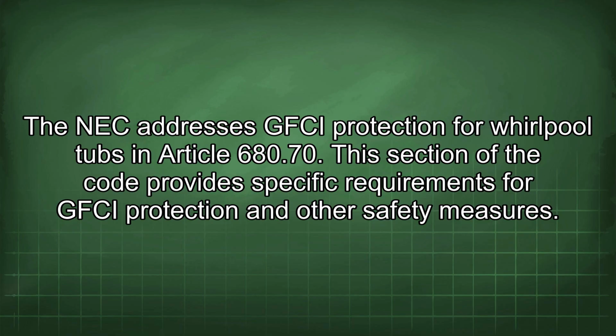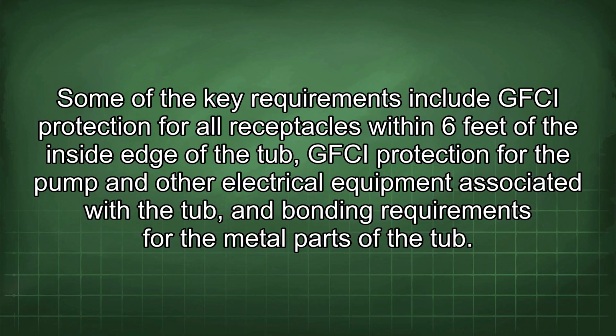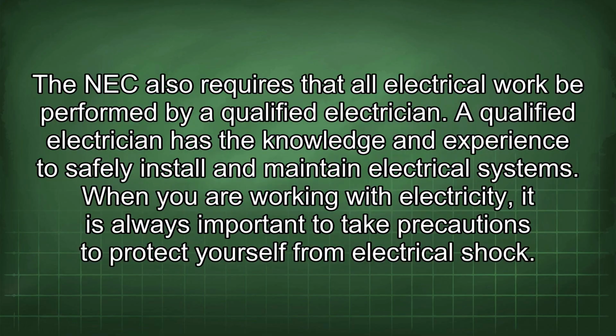The NEC addresses GFCI protection for Whirlpool tubs in Article 680.70. This section of the code provides specific requirements for GFCI protection and other safety measures. Some of the key requirements include GFCI protection for all receptacles within 6 feet of the inside edge of the tub, GFCI protection for the pump and other electrical equipment associated with the tub, and bonding requirements for the metal parts of the tub. The NEC also requires that all electrical work be performed by a qualified electrician. A qualified electrician has the knowledge and experience to safely install and maintain electrical systems.